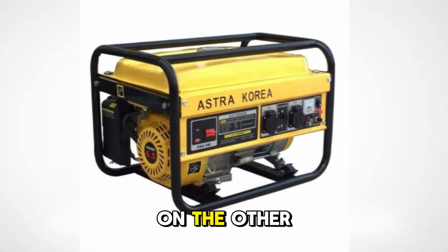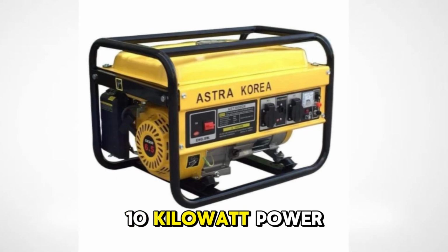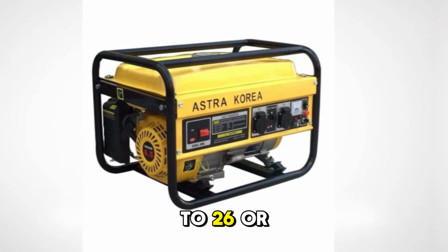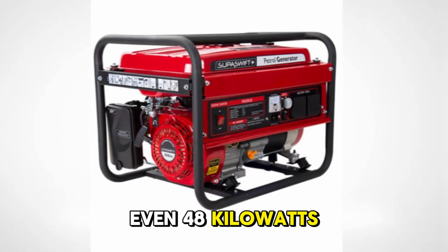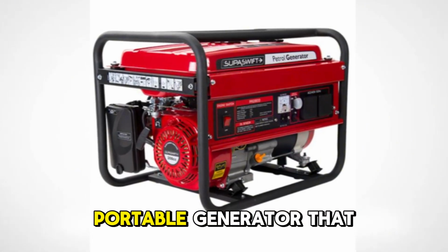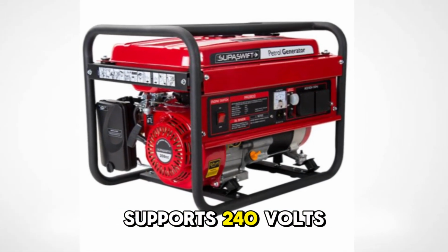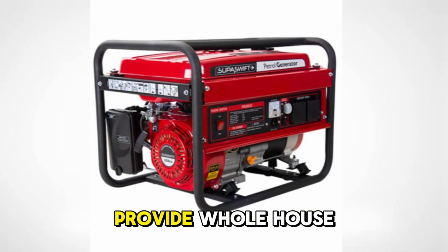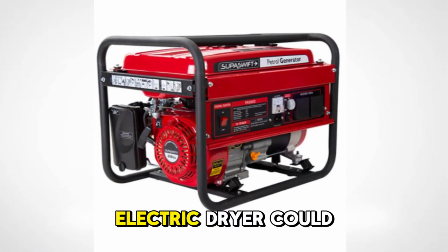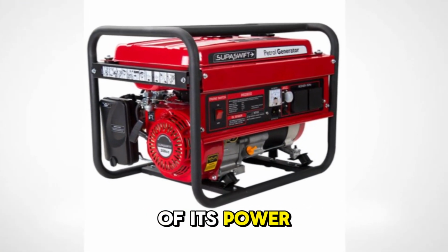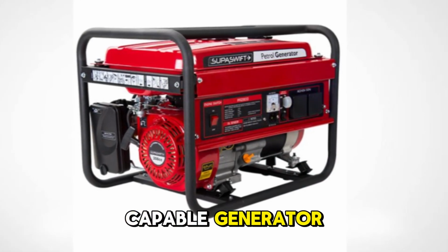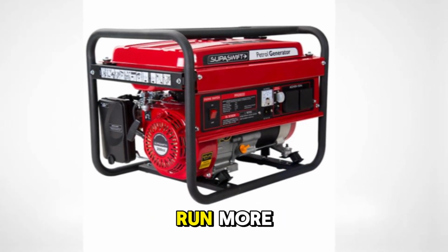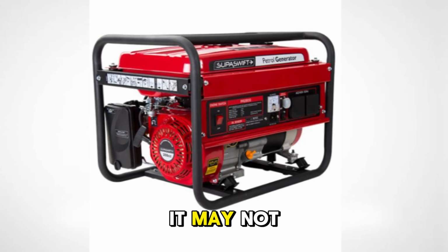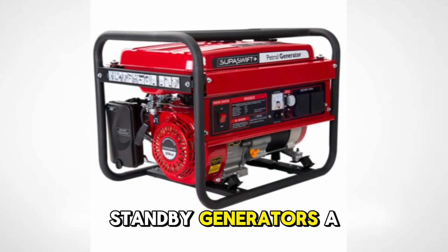Standby generators, on the other hand, start at about 10 kilowatt power output and go all the way up to 26 or even 48 kilowatts. While you might have a 30-amp portable generator that supports 240 volts, it likely won't provide whole-house power—a single electric dryer could demand a majority of its power. A 50-amp capable generator is probably a better choice if you want to run more, and even then it may not be enough.